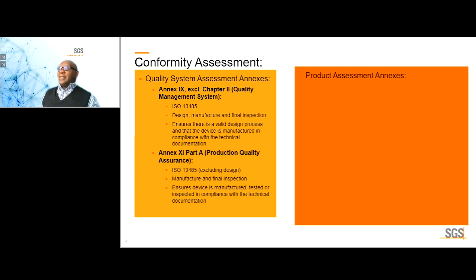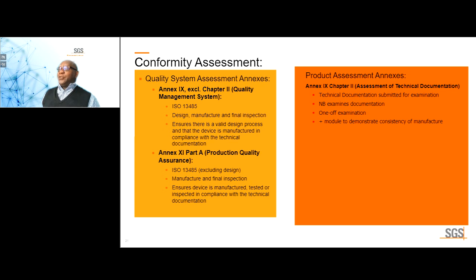Here, we're talking about product assessment annexes, of which there are three, starting with Annex 9, Chapter 2, whereby you need to put together a technical documentation, which has to be submitted for examination. The notified bodies conduct the examination. It's a one-off examination, but as we indicated before, it has to be combined with a module to demonstrate consistency of manufacture. So in this case, you may be going for Annex 9, Chapter 1, combine that with Annex 9, Chapter 2, for instance.